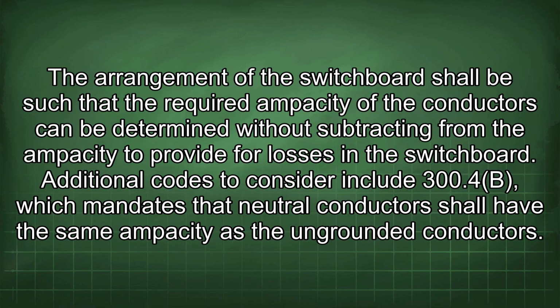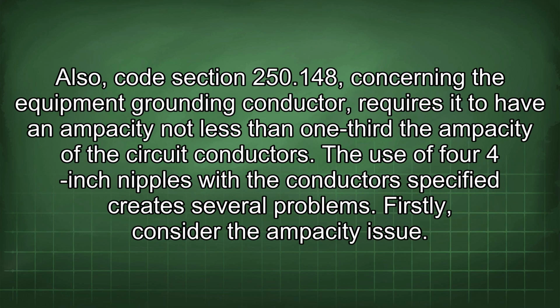The arrangement of the switchboard shall be such that the required ampacity of the conductors can be determined without subtracting from the ampacity to provide for losses in the switchboard. Additional codes to consider include 300.4b, which mandates that neutral conductors shall have the same ampacity as the ungrounded conductors. Also, Code section 250.148 concerning the equipment grounding conductor requires it to have an ampacity not less than 1/3 the ampacity of the circuit conductors. The use of four 4-inch nipples with the conductors specified creates several problems.